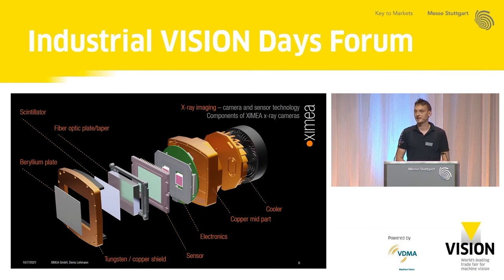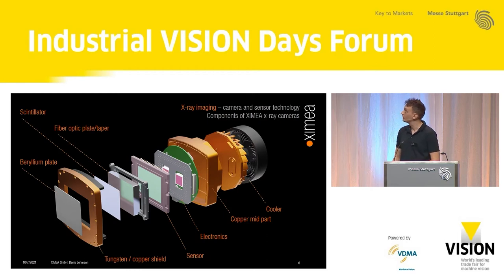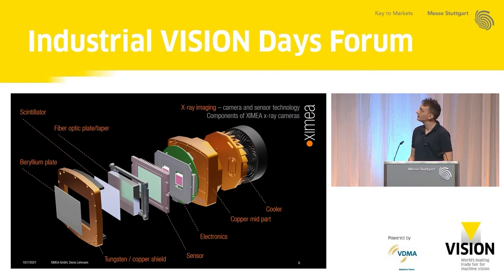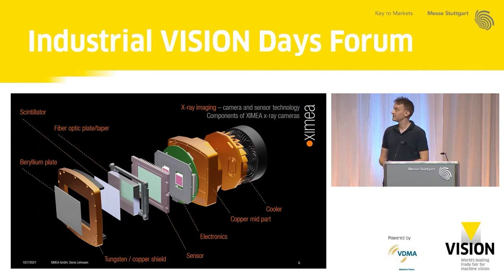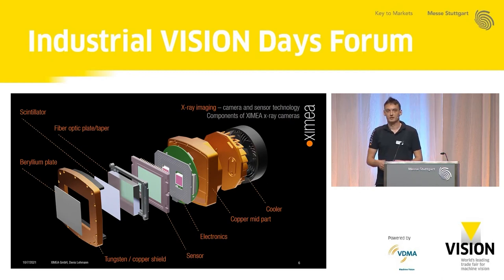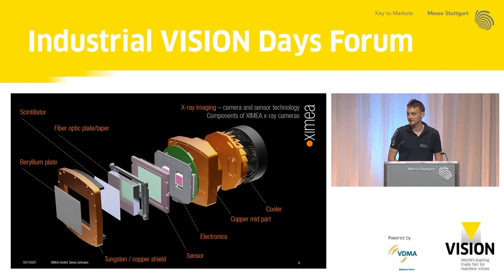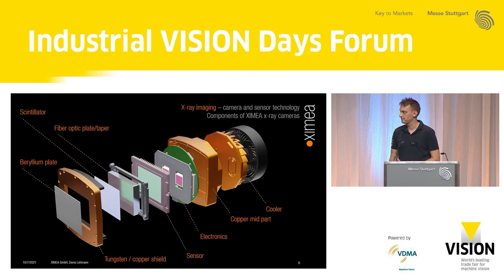A XIMEA X-ray camera looks like this. At the front, you have a beryllium plate — beryllium is transparent, or mostly transparent, to X-rays. X-rays pass through the beryllium plate and hit the scintillator screen, which emits visible light. That visible light is then channeled through the fiber optic plate onto the sensor. We also provide a tungsten-copper shield up front to protect the electronics and sensor from radiation.